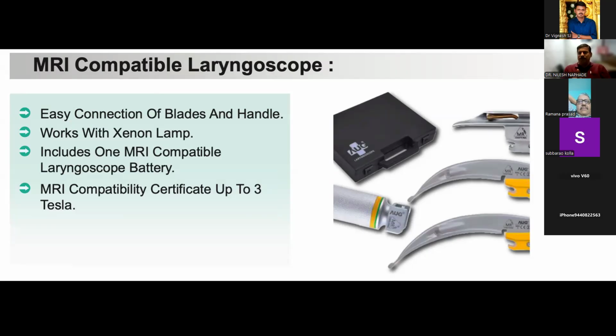Now, always remember, if the laryngoscope or any equipment is compatible with 3 Tesla, it can go with a 0.3 Tesla machine. If it is compatible with a 3 Tesla, it can be used with a 1.5 Tesla machine. If it is compatible with bigger magnet, it can work with a smaller magnet. But one which is compatible for a smaller magnet cannot be used with a bigger magnet MRI machine. Remember that.